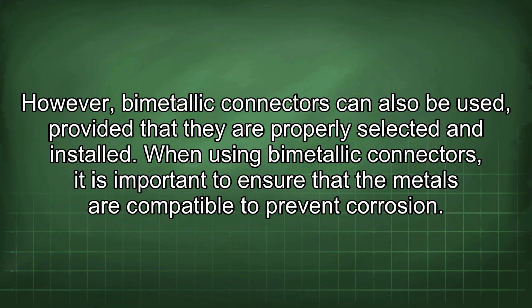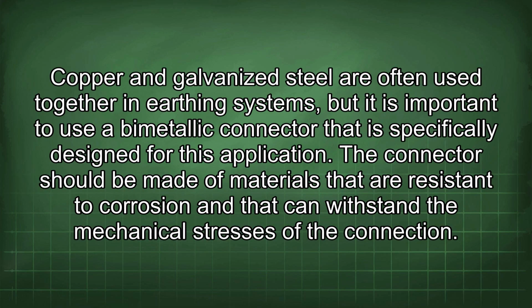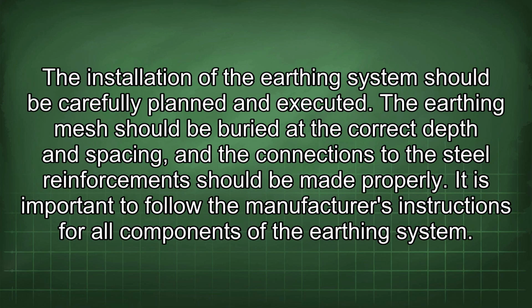When using bimetallic connectors, it is important to ensure that the metals are compatible to prevent corrosion. Copper and galvanized steel are often used together in earthing systems, but it is important to use a bimetallic connector that is specifically designed for this application. The connector should be made of materials that are resistant to corrosion and that can withstand the mechanical stresses of the connection. The installation of the earthing system should be carefully planned and executed.